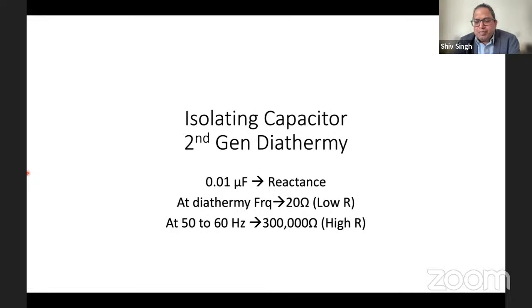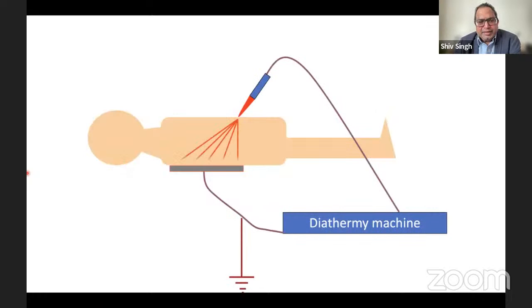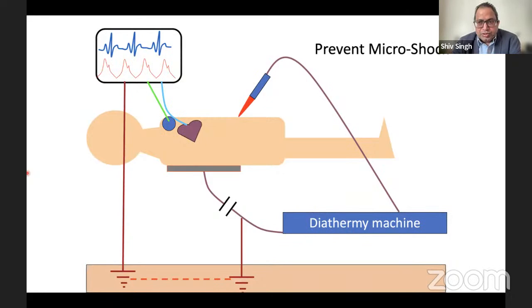So what we did in this case was they said, okay, earth is bad, but we can add an isolation capacitor to the system. When you're using diathermy, because it's a high frequency current, it will flow through it and complete the circuit. But what if the patient was connected to intracardiac catheters, or an ECG with an earthed monitor? In that case, the current cannot flow through this, and that's good. You've prevented the microshock. But what about if there is a disconnection?